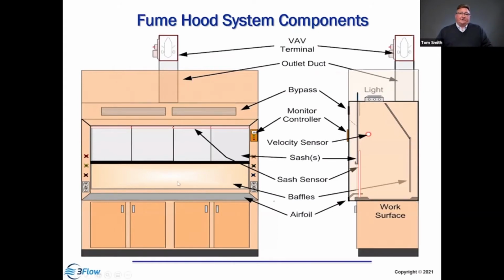We look into the hood and at the hood to determine whether it has the appropriate components. As I mentioned earlier in a slide, the airfoil sill is very important. It fits over the work surface and helps to streamline flow into the hood. Then at the back of the hood, we have the baffles. And the baffles have slots for controlling the airflow distribution within that hood. Our vertical sliding sash moves up and down. And so you can open and close the sash to restrict the opening, or it may have horizontal panels that move left to right. So vertical goes up and down, horizontal panels move left to right.